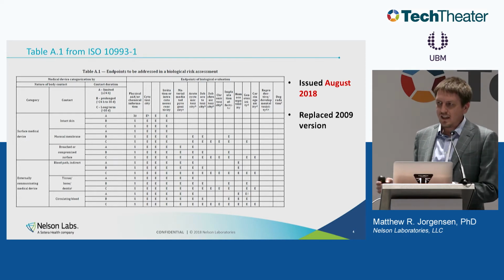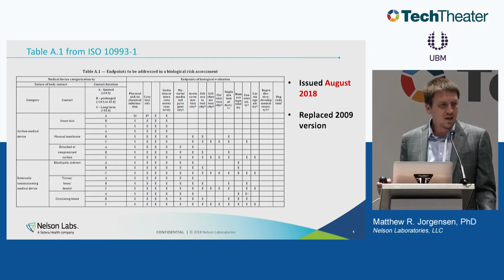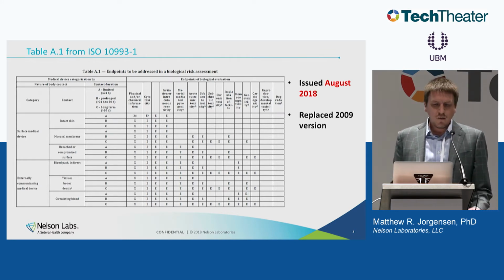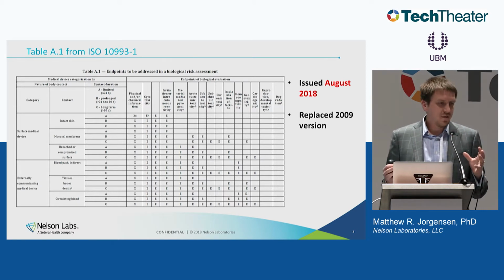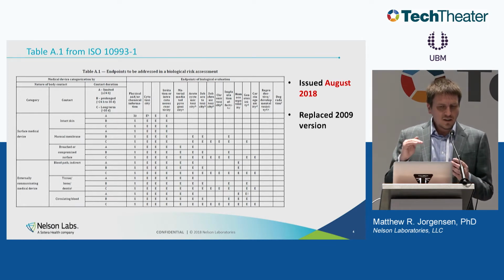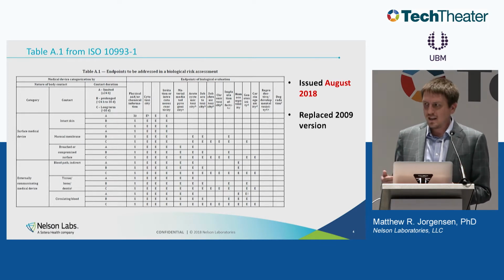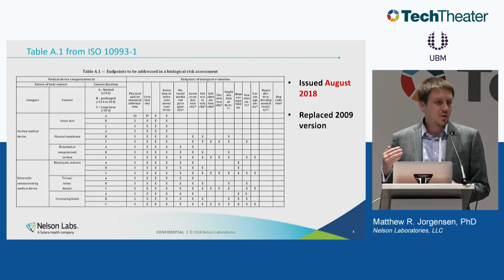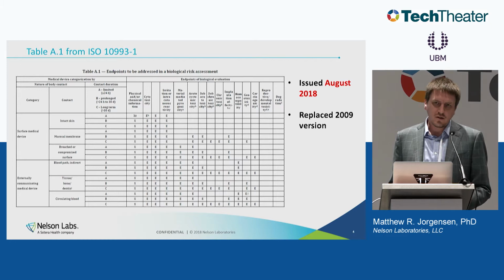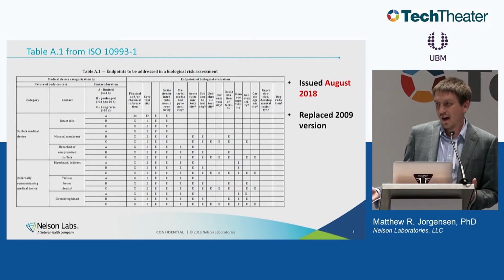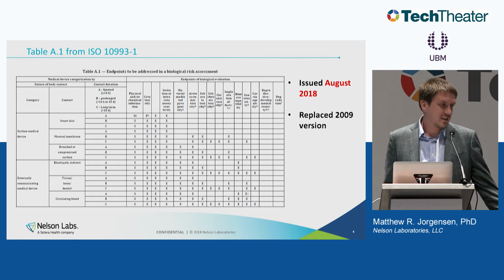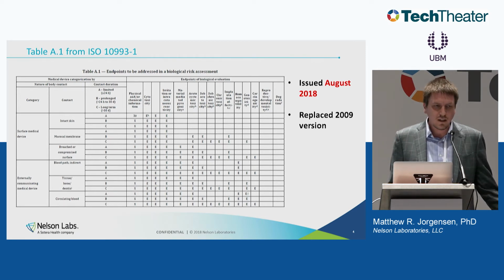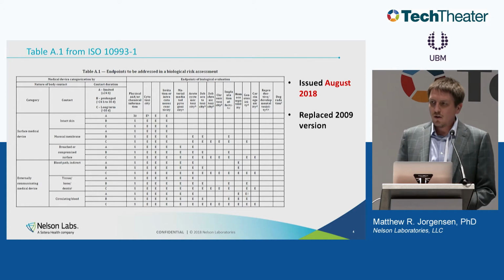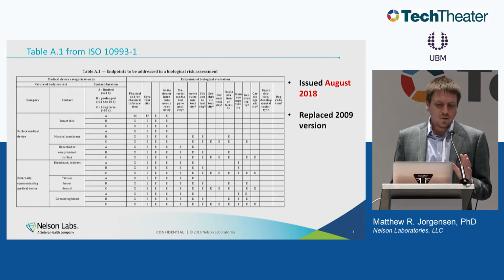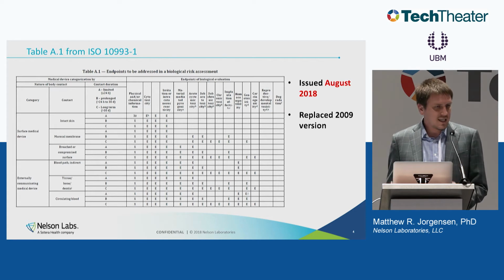And so now we're in a place, and we were doing this over the last couple of years leading up to the release of this document. What this really means is that for a certain type of device, you can pick any of those categories that you want. Just because there's an E in those columns, it doesn't mean that you need to test that. It just means that you need to address it or evaluate it. And we found that there's lots of situations where we can address or evaluate a biological risk with no testing, maybe by leveraging the clinical history, the use of the device and the materials, or other routes to address it. So these things just need to be evaluated, not necessarily tested.